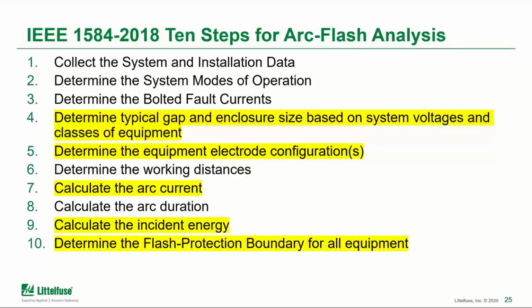Then to determine the working distances, it's really the same as the 2002 standard for the most part. There's a table with the defaults, but there's now a minimum 12-inch working distance. The calculation of the arc current, step number 7. This one is where the determination of your system modes comes into play. It's not always simple because you may have time varying sources, such as generators, or maybe limited time sources like induction motors that can feed back. And then number 8, looking at the arc duration. And number 9, the incident energy.